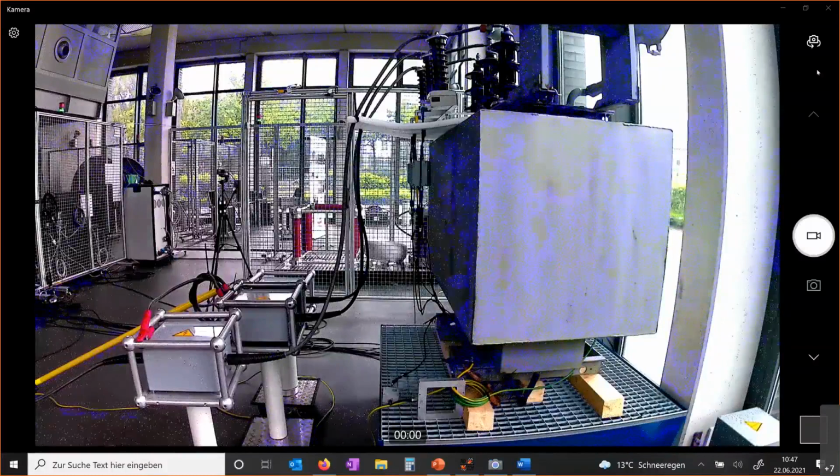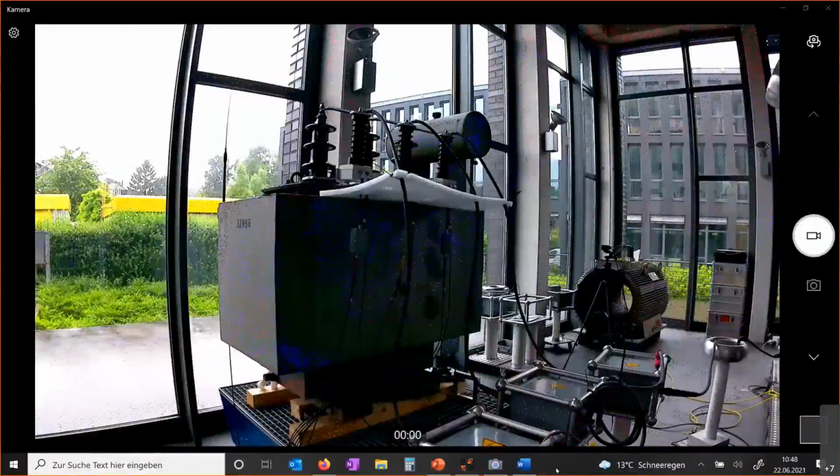Additionally, I would like to make a conclusion about some of the things my colleague mentioned. Again, to reiterate, this measurement is done via the tap sensor, or it can be done via a coupling capacitor, like done here in the setup, which lets you use the IEC 60270 recommended range at low frequency, below 1 megahertz. This frequency range detects most of the problems throughout the power transformer. Additionally, using the UHF sensor, only local, nearby problems can be detected. It cannot detect problems deep in the winding.